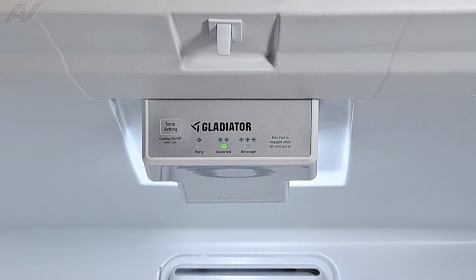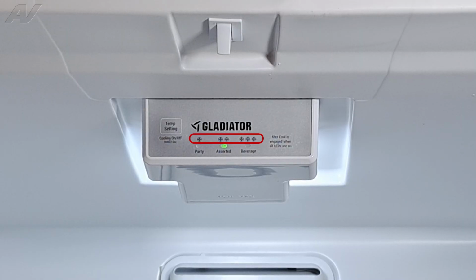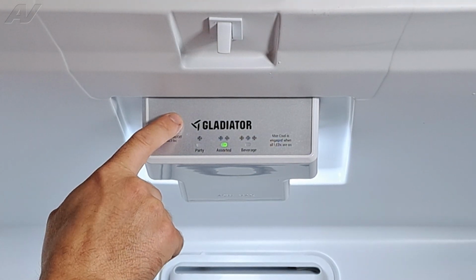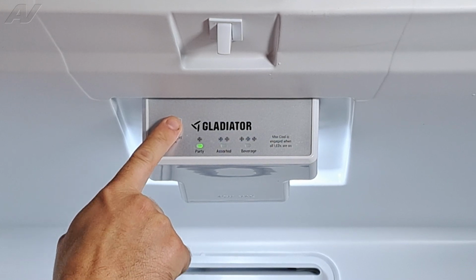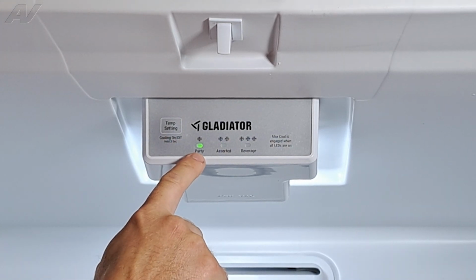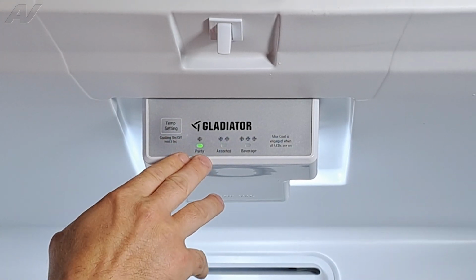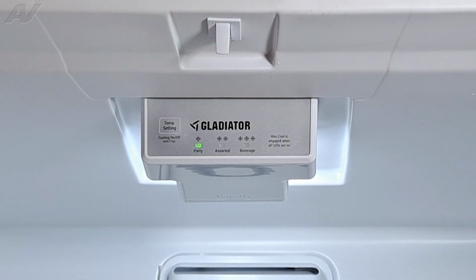To enter diagnostics, it's actually pretty easy. So what we'll have to do is look at the control panel up there. You'll see a set of snowflakes, and these snowflakes are actually numbered LED 1, 2, and 3. So to enter diagnostics, you're going to want to keep pressing your selector button until the snowflake keeps going until just the first LED all the way over to the left is illuminated.